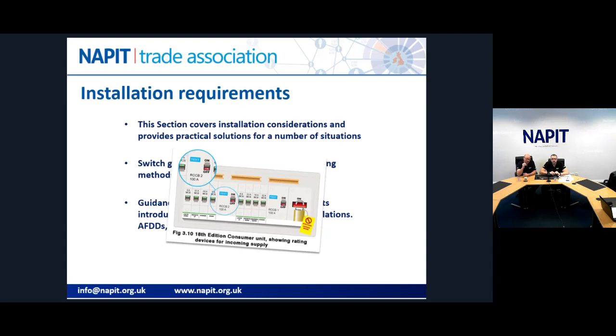And right up to date, we've got the 18th edition consumer units, and what they are really is there's a requirement now for RCBOs and things like that to have overload protection, and we can't solely use diversity anymore. So the issue is, if you were to put a consumer unit straight onto the DNO supply and it was a 100 amp supply, are those devices now protected by that 100 amp fuse?